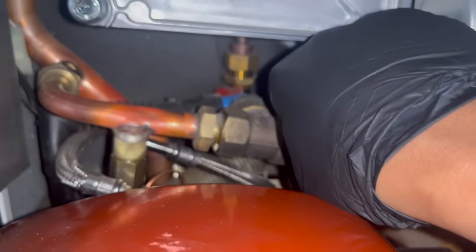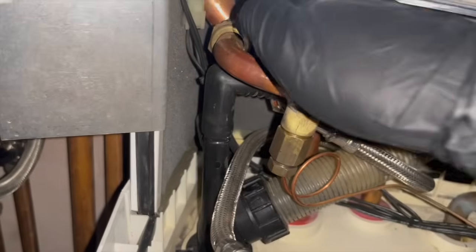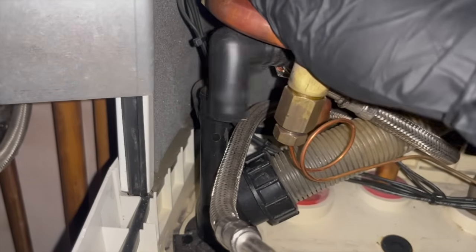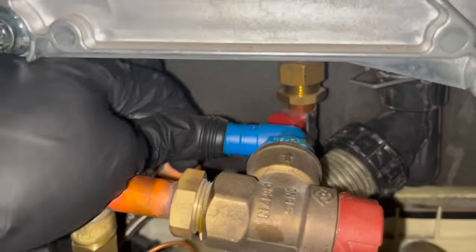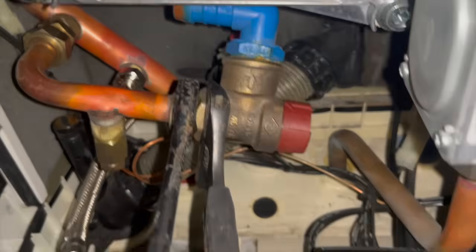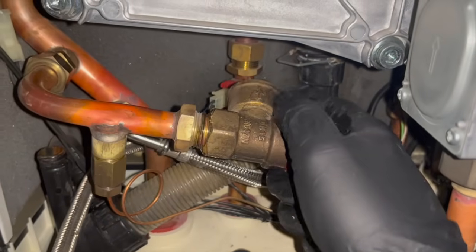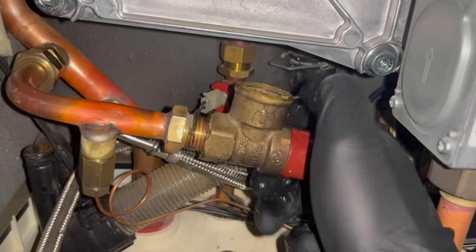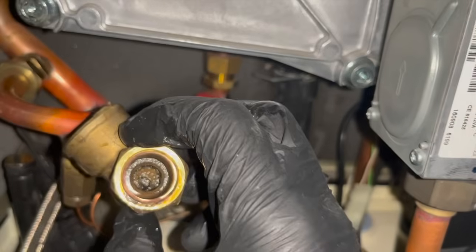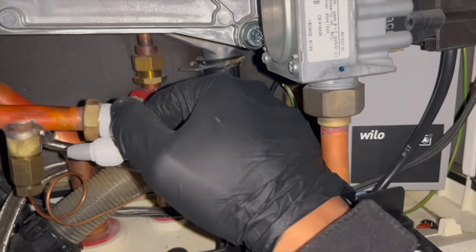I can see the PRV is there. I'm going to drain down the boiler using the PRV because I'm going to be changing it anyway. I've disconnected the vessel by undoing the nut at the top. Now that it's out of the way I can take out the PRV. First thing is to take off the little black rubber tube, then rotate the PRV towards us and spin out that little plastic elbow. Finally we can unscrew the PRV. Now we can put some PTFE around the thread and put the new PRV in.